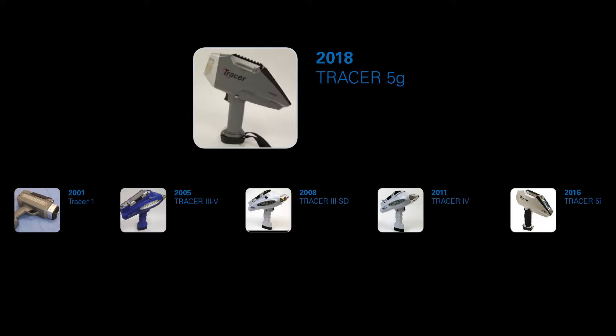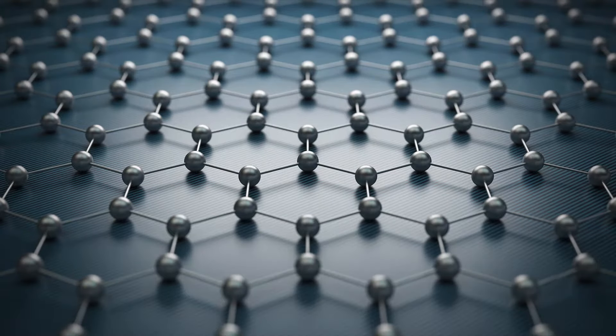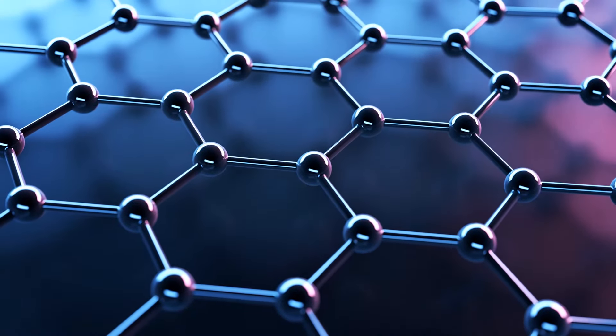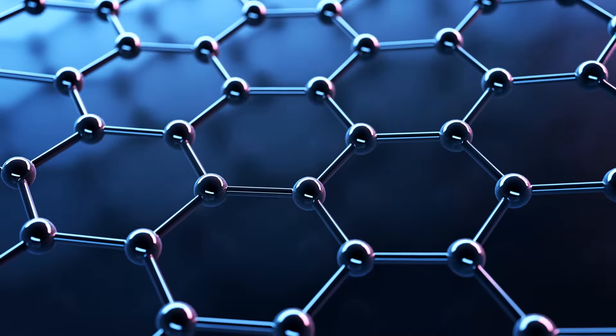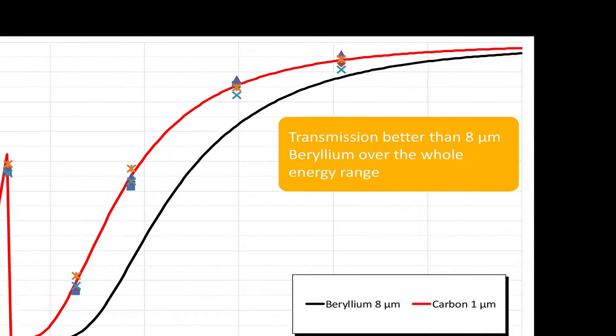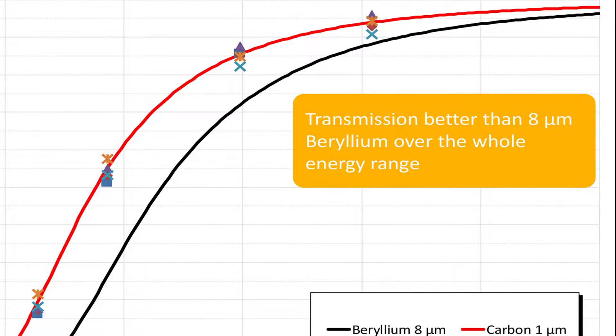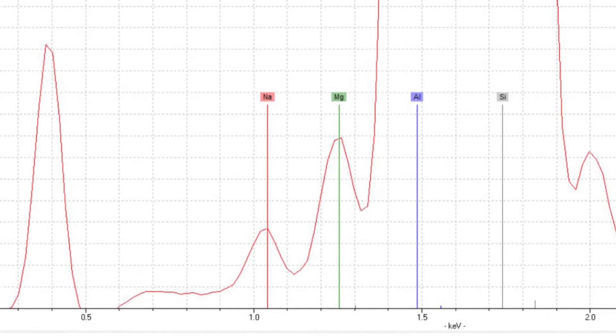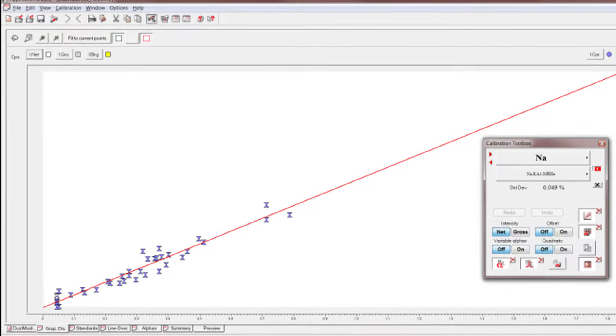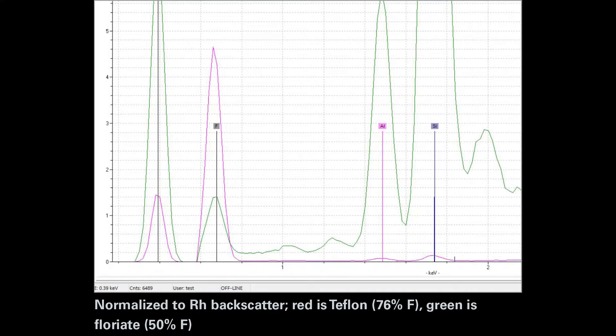The Tracer 5G is the latest development in the Tracer family. It incorporates the new graphene window detector introduced by Moxtek, a leading supplier of x-ray detectors. This groundbreaking window is one of the first commercial applications of graphene, an advanced material composed of atomic layers of carbon atoms arranged in hexagonal lattices. While the graphene window is only one micrometer thick, this advanced material is extremely strong because of its crystalline nature. The major advantage of this new detector is that the transmission of low-energy x-rays is substantially increased, improving detection sensitivity for light elements such as sodium, magnesium, aluminum, and silicon. Using this detector and helium flush on the Tracer 5G, we have achieved sodium detection limits of under 275 parts per million and magnesium detection limits of under 100 parts per million. In addition, this configuration gives the instrument the ability to detect high levels of fluorine.